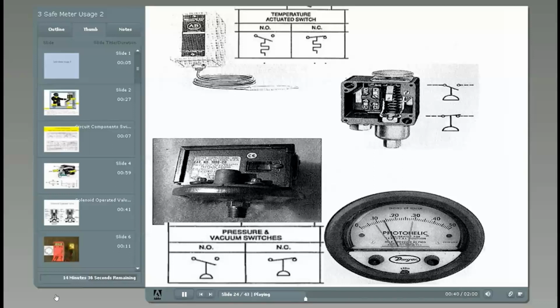The device at the top right is a pressure switch. It can be used to ensure that the oil pump is on so that there is hot oil flowing or to control the operation of an air compressor. The normally open NO contact will close at the selected pressure, and the normally closed NC contact will open at the selected pressure. If this pressure switch was set to 100 psi, the NO would close at pressure rise of 100 and above, and the NC would open at pressure rise of 100 and above.